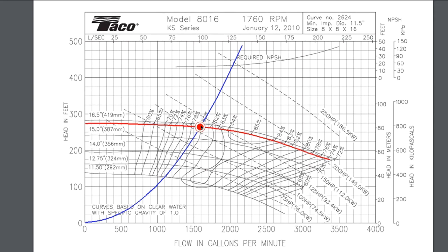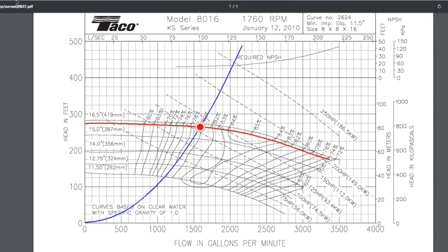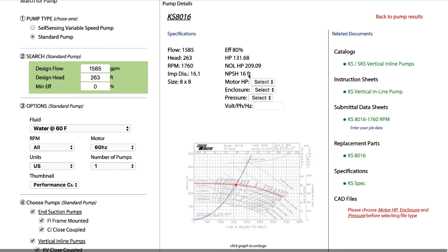There's also a line labeled required NPSH. Going up from our design flow rate and across, that tells us the required NPSH is in the neighborhood of 15 feet. Going back to the specifications page, it said we'd need an NPSH of 16 feet — so our reading of 15 feet was pretty close. It also said we'd need 132 horsepower at the operating point — somewhere between 125 and 150 — and 80 percent efficiency. So this might be a good choice for our pump.